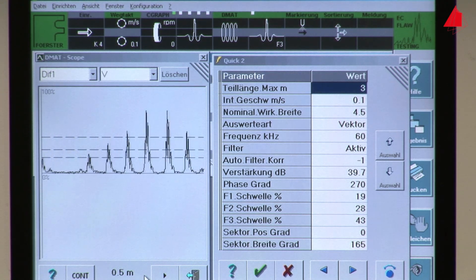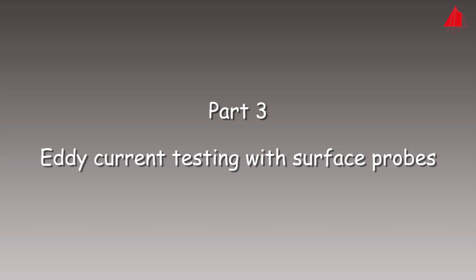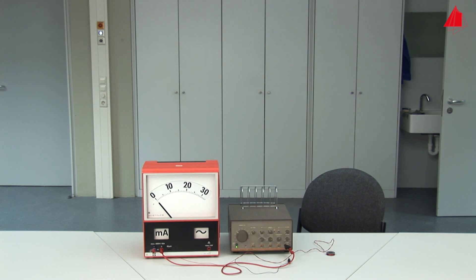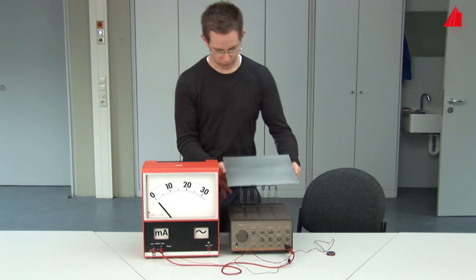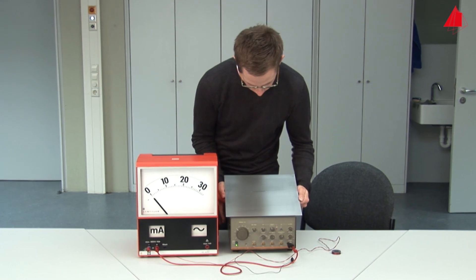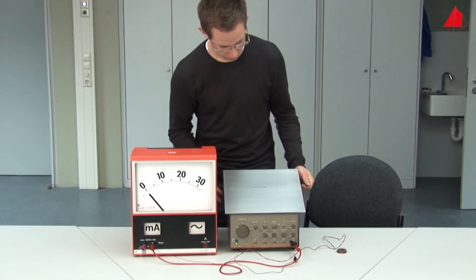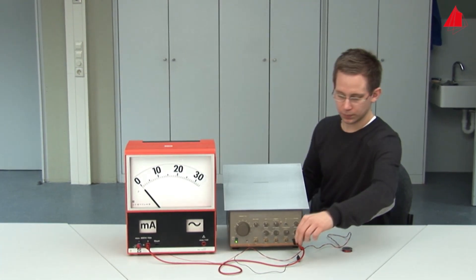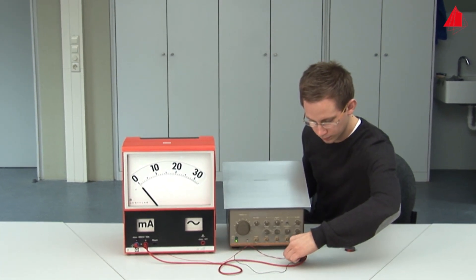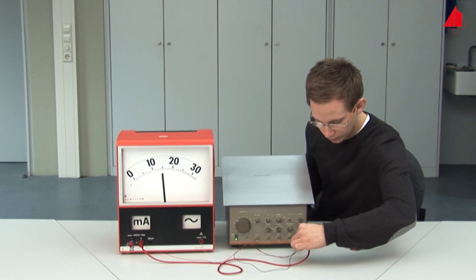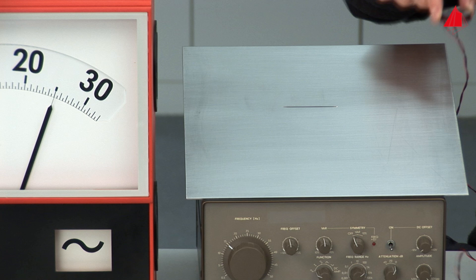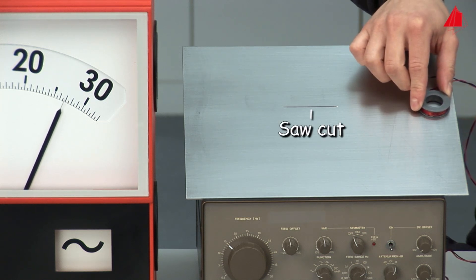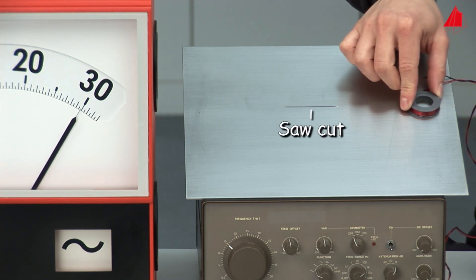For determining the circumferential location of defects, another version is needed: eddy current testing with surface probes. We want to show this version in the laboratory too. Here the test piece is not a tube but a sheet, again made of an austenitic steel, with a saw cut in the middle going right through the sheet. In contrast to the coaxial probes, the coil is not pushed over a tube but instead placed with its flat side on the surface of the test piece.